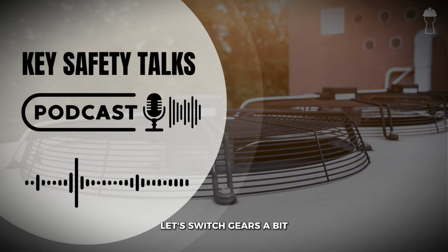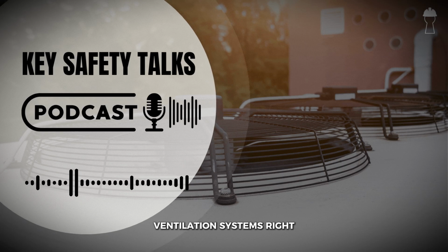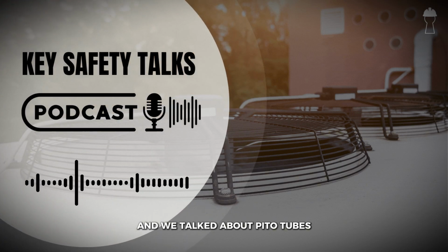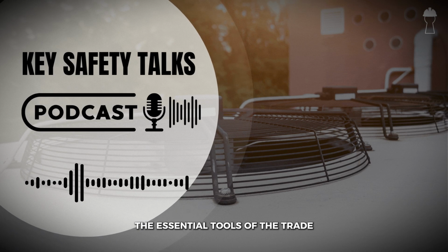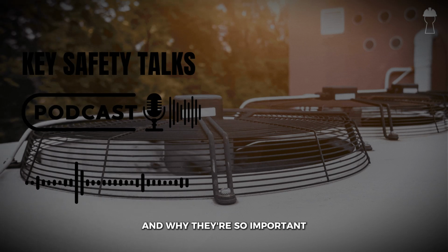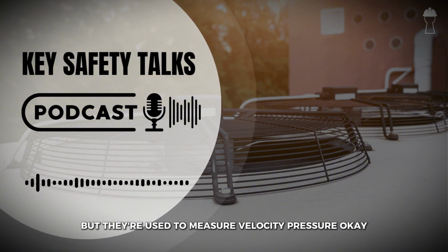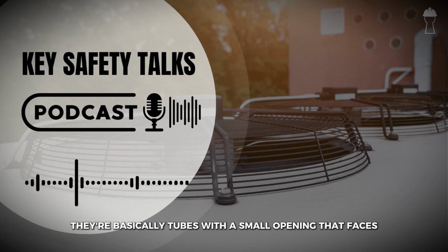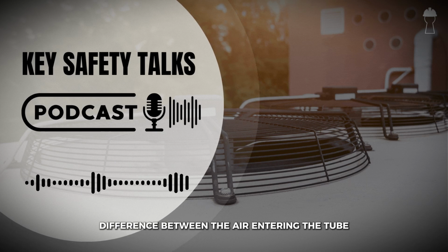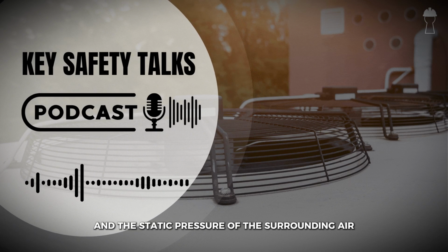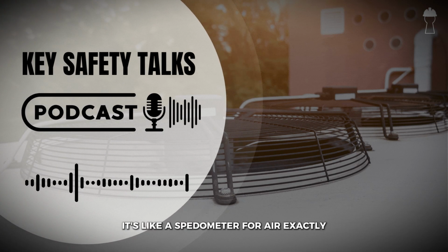Okay, so now let's switch gears a bit and talk about those instruments used to measure and monitor ventilation systems. Right. We talked about pitot tubes, rotating vane anemometers, and thermal anemometers earlier. Right, the essential tools of the trade. Can you elaborate on how they're actually used and why they're so important? Sure. So pitot tubes are simple devices, but they're used to measure velocity pressure. Okay. They're basically tubes with a small opening that faces the airflow. And by measuring that pressure difference between the air entering the tube and the static pressure of the surrounding air, we can figure out the velocity pressure, which tells us how fast the air is moving. It's like a speedometer for air.